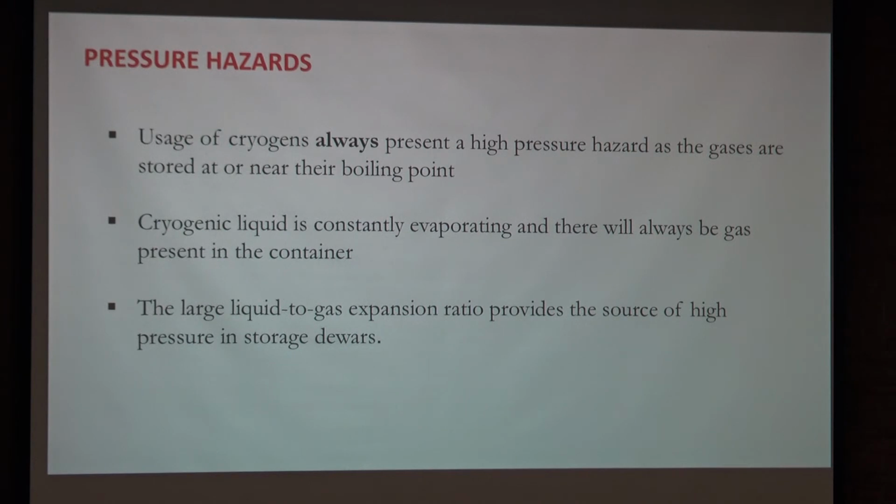You cannot allow a pressure buildup inside your dewar, either deliberately or accidentally. Most transfer dewars come with an emergency pressure release that will pop automatically once the pressure exceeds a certain threshold. But there is, of course, a danger that this freezes over under certain conditions.